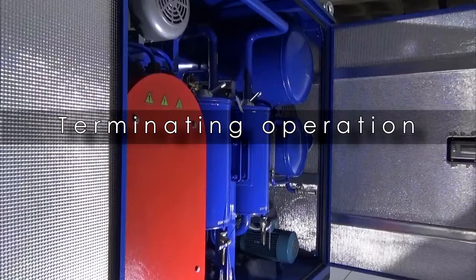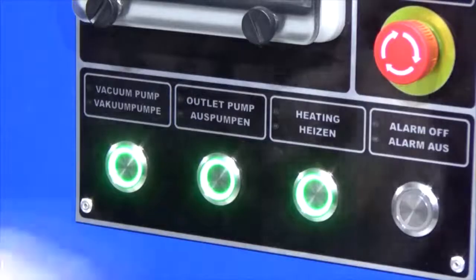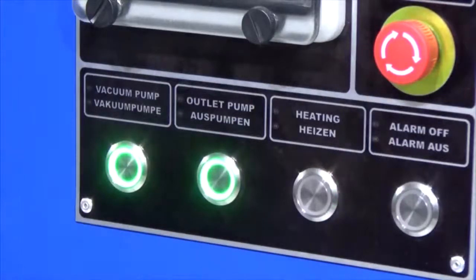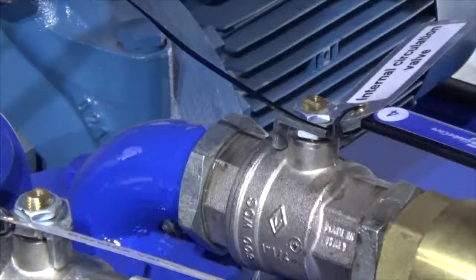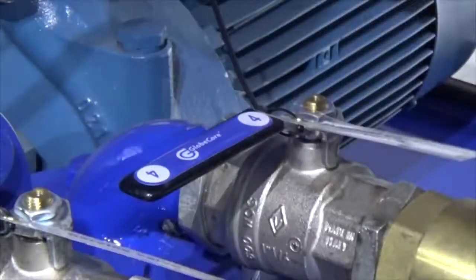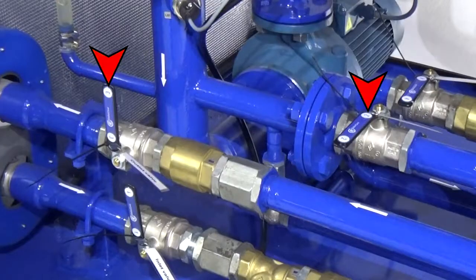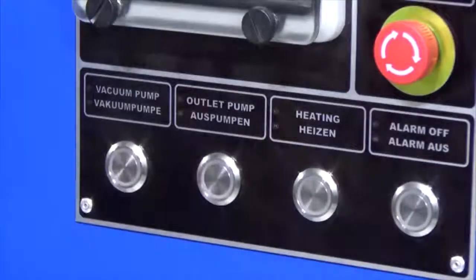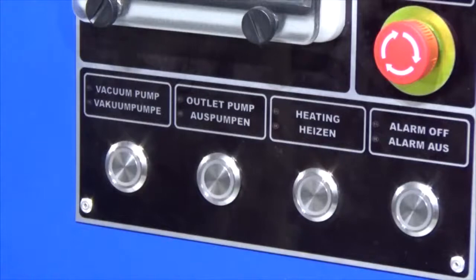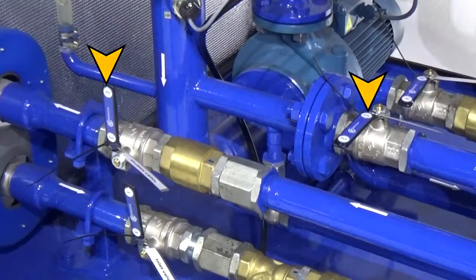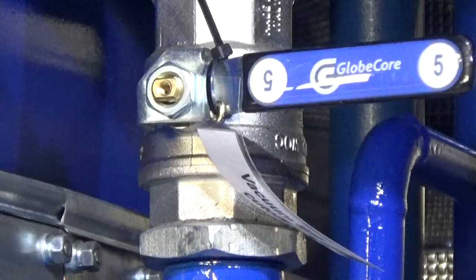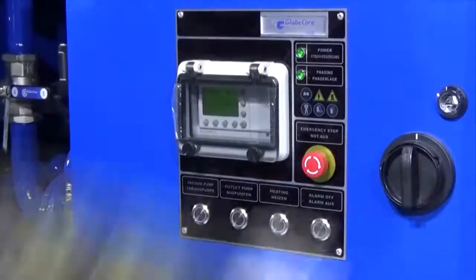Terminating the operation. 1. Disengage the heater by pressing the heating button about 5 to 10 minutes before shutting down the unit to prevent overheating of oil in the heater chamber. 2. Stop the vacuum pump by pressing the vacuum pump button. 3. Close valve MV4 and open valves MV2 and MV3. 4. After the outlet pump drive stops, disengage the pump by pressing the outlet pump button. 5. Close valves MV2, MV3, and MV5. 6. Turn the power handle to the off position.